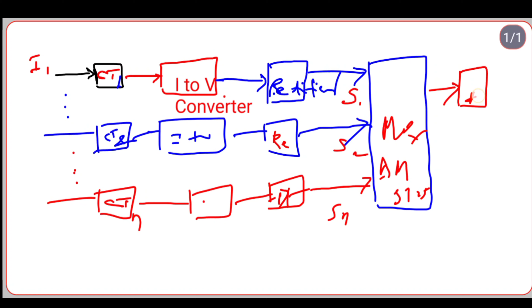Let us see the block diagram clearly. The block diagram of the microprocessor based overcurrent relay you can see clearly in this diagram. The current will flow through the current transformer, the CT. These are also known as instrument transformers. You studied it. Using multiplexer and microprocessor we are developing microprocessor based relays. If fault current in any circuit exceeds the pickup value, the microprocessor sends a trip signal to the circuit breaker. That is the purpose of the trip signal to the circuit breaker.